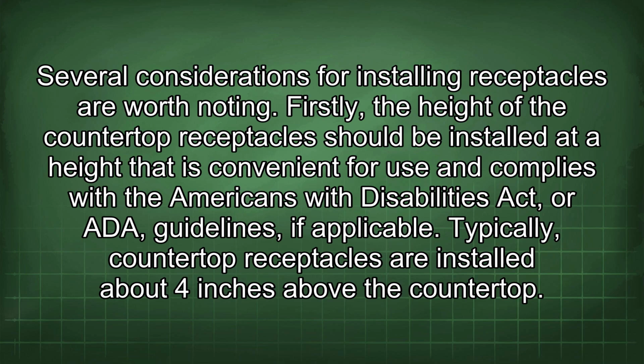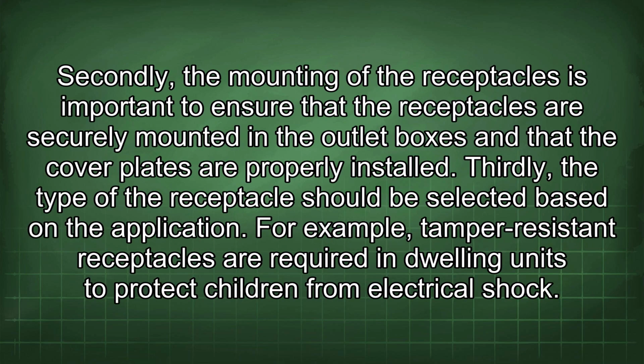Firstly, the countertop receptacle should be installed at a height that is convenient for use and complies with the Americans with Disabilities Act, or ADA, guidelines, if applicable. Typically, countertop receptacles are installed about 4 inches above the countertop. Secondly, the mounting of the receptacles is important to ensure that the receptacles are securely mounted in the outlet boxes and that the cover plates are properly installed. Thirdly, the type of the receptacle should be selected based on the application. For example, tamper-resistant receptacles are required in dwelling units to protect children from electrical shock.